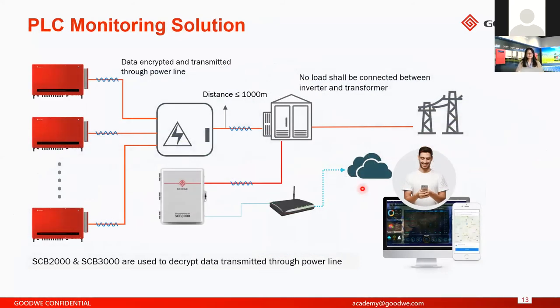And next I'm introducing the PLC monitoring solution. PLC stands for power line communication. As you can see, there is no extra communication cable or module you have to install on the inverter. There is a PLC board integrated inside the inverter. As an installer, you can just connect all your AC cables, and then the data collected and generated by the inverter will be transmitted through the cables. But the data are encrypted in the process of transmission, and then it needs our SCB2000 smart communication box to decrypt the data. So the data can be transmitted to the GoodWe server and then presented on the SEMS portal.